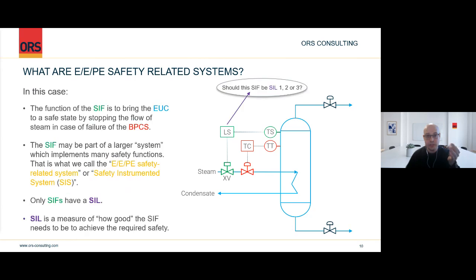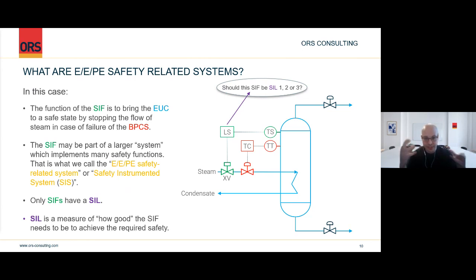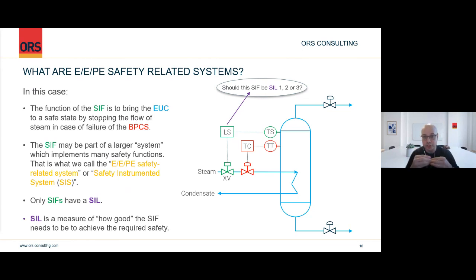So what is SIL? SIL is basically how good that safety instrumented function needs to be so that you can ensure functional safety and overall safety. When you combine that safety instrumented function with other protection layers in your system, that achieves overall safety. Functional safety requires that function to achieve the required SIL — not only during the design stage, but also during operation and maintenance. The SIF may be part of a bigger system, the safety instrumented system, within which there may be several safety instrumented functions, each one with a SIL — which could be SIL 1, SIL 2, SIL 3, or if something else is needed.